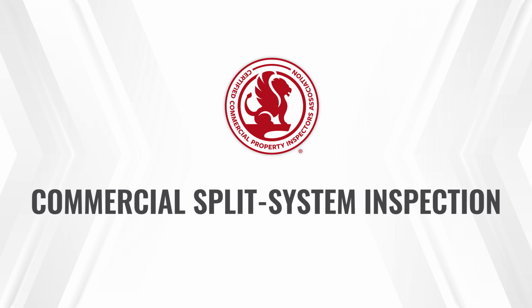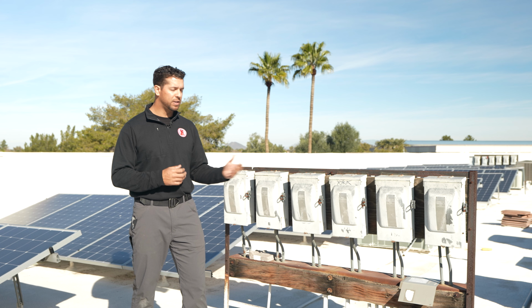So we've talked about a couple different approaches to inspecting HVAC on a roof. Now I want to talk about some CommSop requirements we want to make sure we're finding and noting in our report. Labeling is very important, and it's listed in the CommSop under cooling that these service disconnects should be labeled to correlate with each unit, so they can be shut off safely for maintenance and repair. I don't see legible labeling here, so I'm going to note in my report that this should be taken care of.